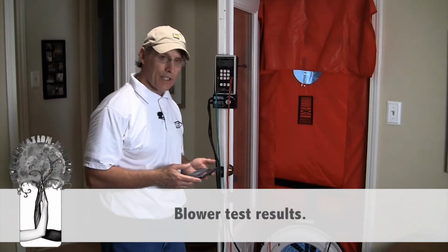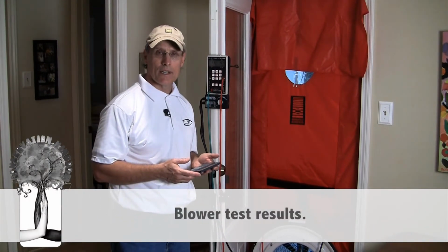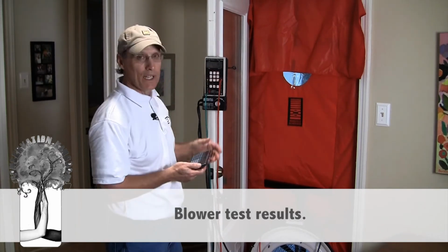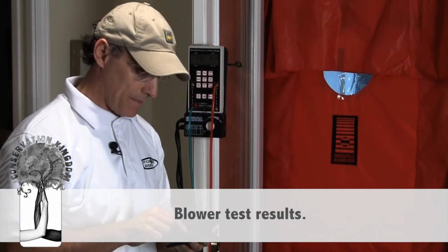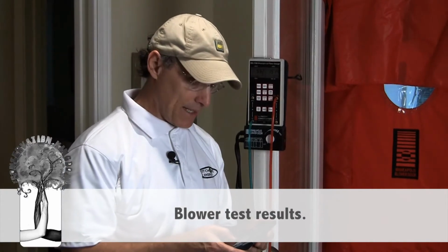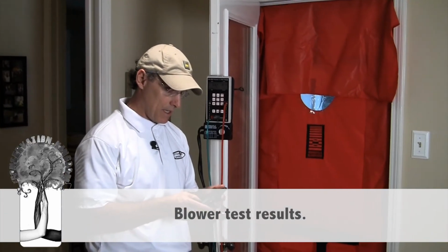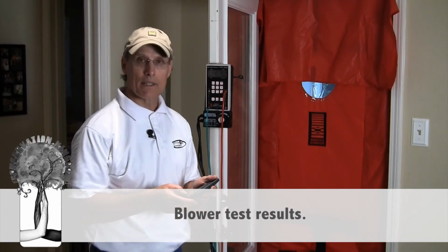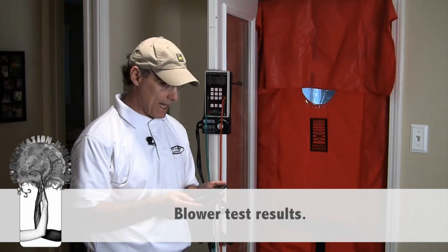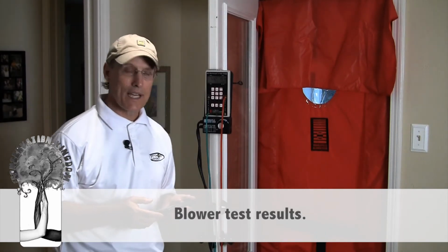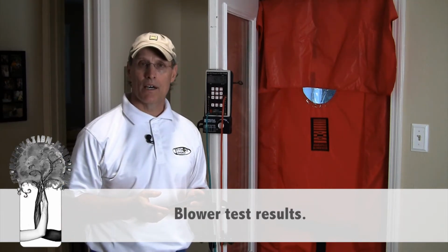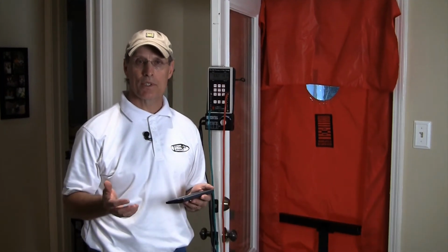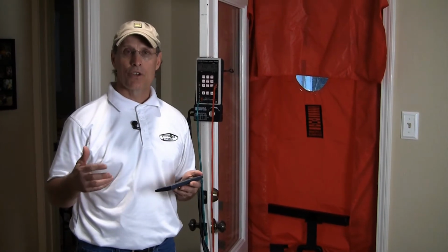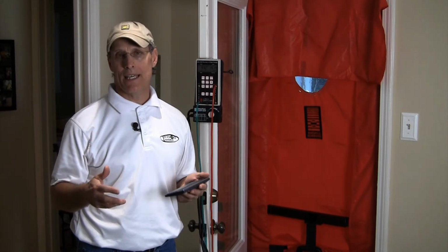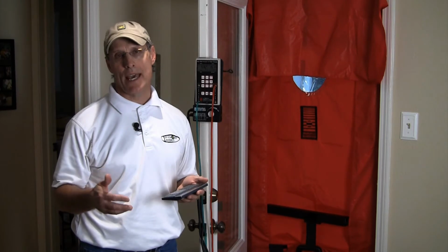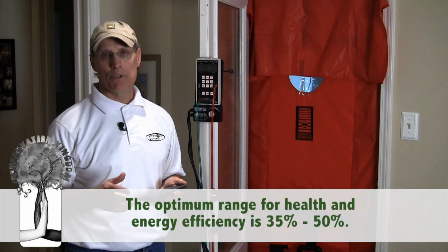Okay, so now let's look at what the percent leakage of this house is. So we've got 1,514 CFM of leakage, and we're now going to divide that by the volume of the house and then multiply by a constant that is determined by other factors on the house. And we find out that this house has 36% of the air in the house, 36% of the volume of the house, turns over naturally every hour. We call that ACHN, air changes per hour natural. And that's good. That's right where you want it.